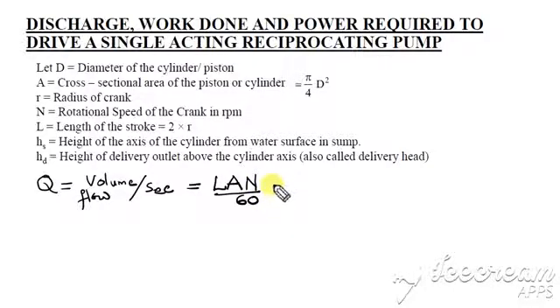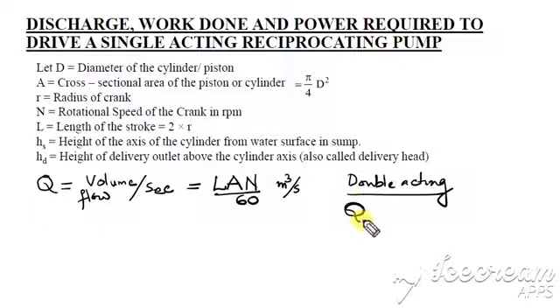For a double acting pump, discharge is approximately twice this expression. However, if you consider the cross-sectional area of the piston rod, the expression will be slightly different. For one side of a double acting pump, Q = LAN/60. But on the other side, the piston rod area must be subtracted from the cross-sectional area of the piston.